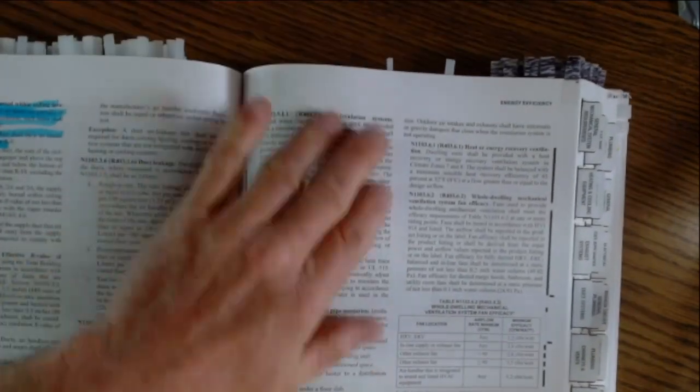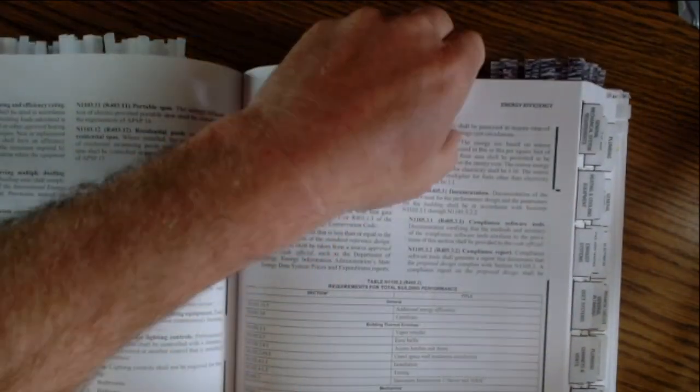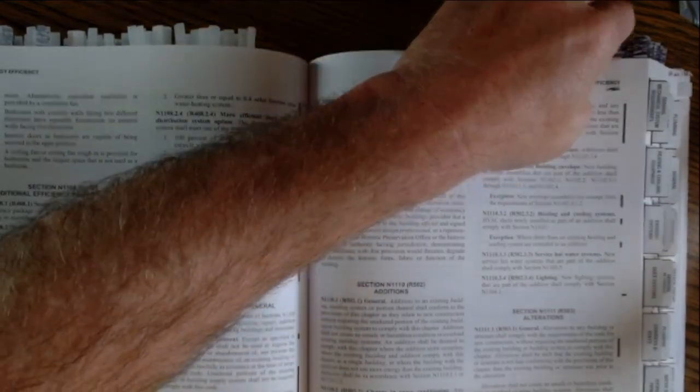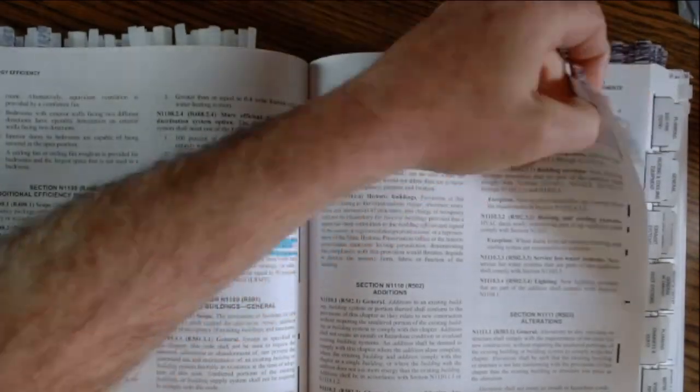Ducts buried. Okay, so R8, make sure your ducts have an R8 minimum if they're buried below the insulation in your attic. If you have a mechanical system and you're above 105 or below 55, you need at least R3 on your piping. That's one they'll get you on. Let's see. ERV. Yeah, just know these percentages, 75% here.